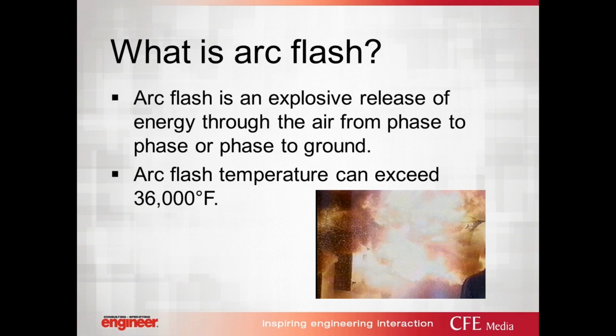The NFPA states that temperatures of an arc flash can exceed 35 K, and in fact have been tested to exceed 36,000 degrees Fahrenheit, which actually happens to be hotter than the surface of the sun. During an arc flash event, copper can expand up to 67,000 times its original volume and hurl shrapnel at over 700 miles per hour. So why do we need mitigation?